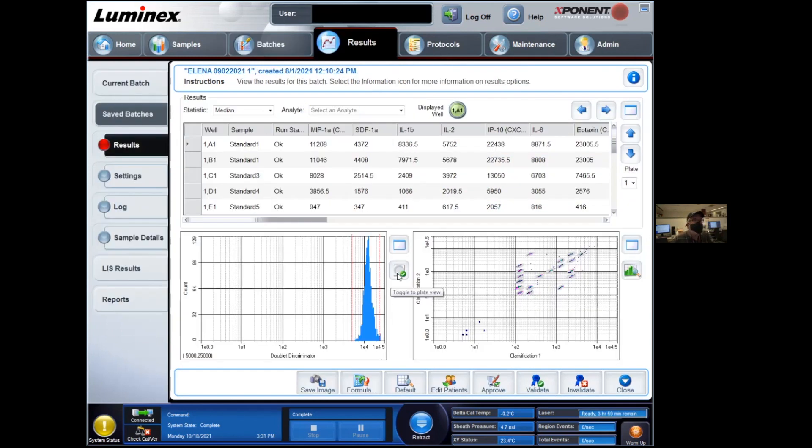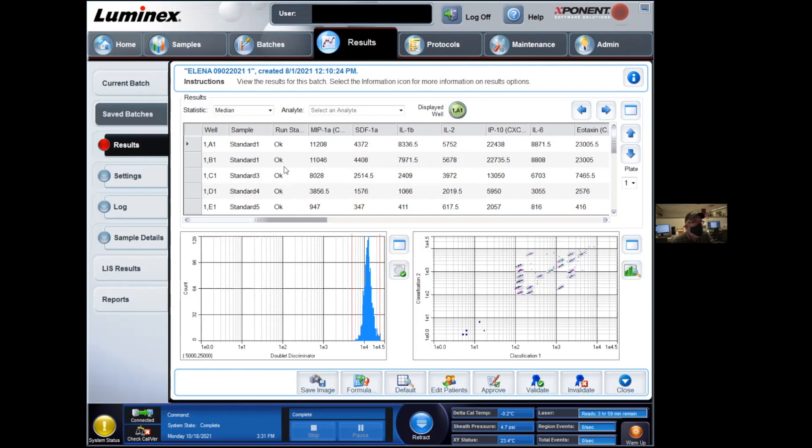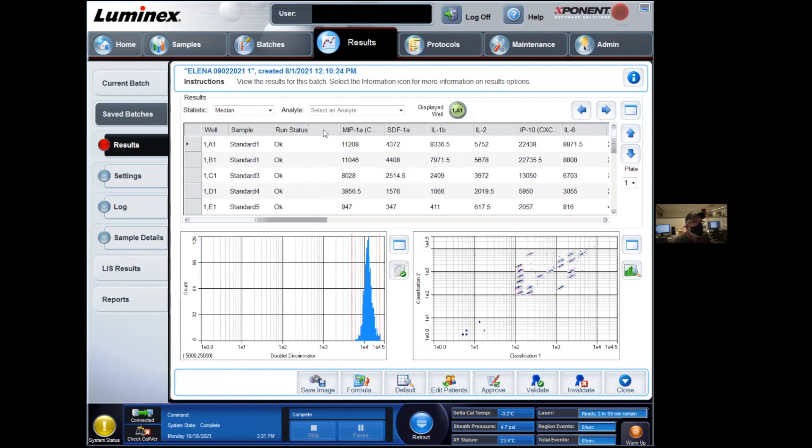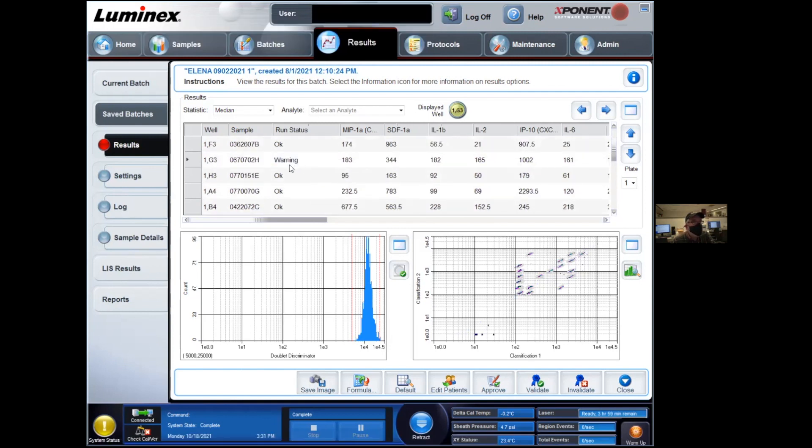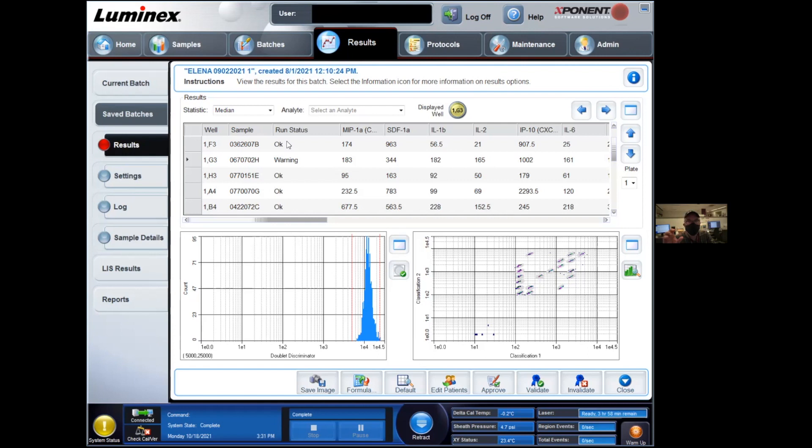So as you run your plate, you're going to get something like this. This window will basically list the fluorescent values as they are being measured for each of the different analytes that you are looking at. In general, you'll have a run status column that lets you know if everything was run properly. Every now and then you'll get a warning telling you that something went wrong. Very often this warning is triggered by the fact that you didn't reach the lowest threshold of bead count before we moved on to the acquisition.